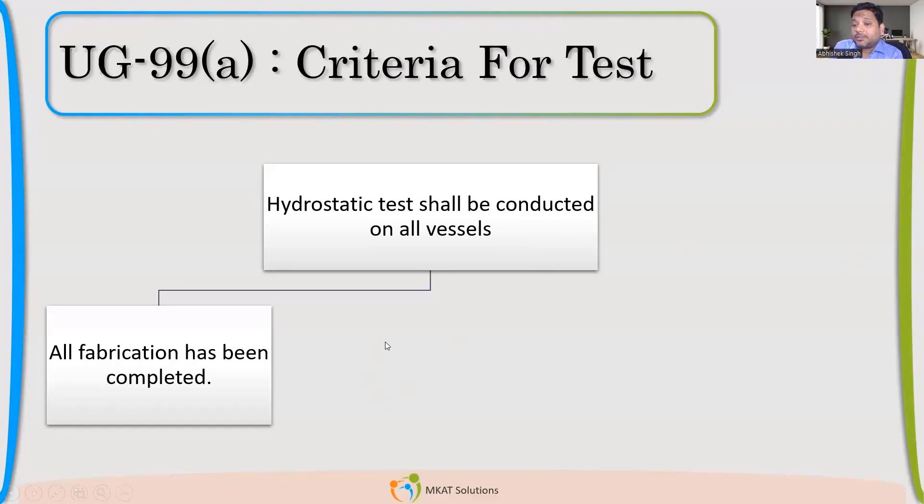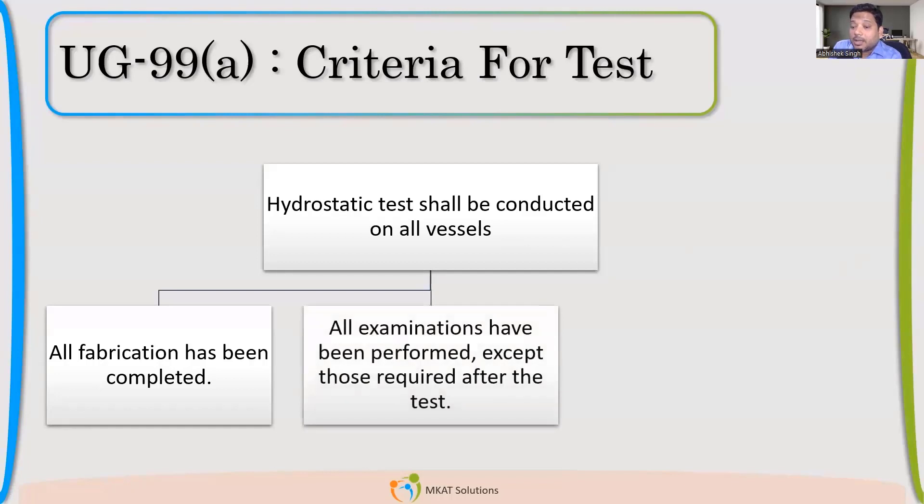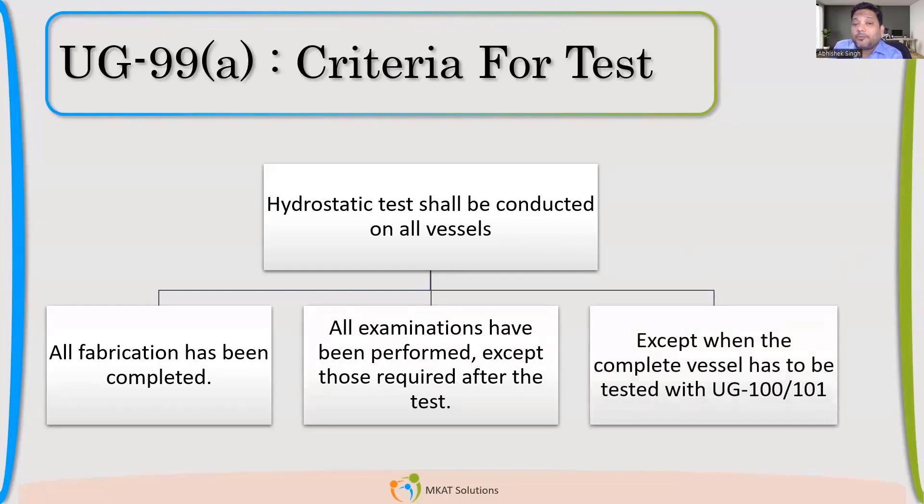Hydrostatic test shall be conducted on all the vessels after the fabrication has been completed. All examinations like radiography, PT (penetrant testing), and dye penetrant testing — all these things have been done. So after all the examinations have been performed, then you should go for hydro.